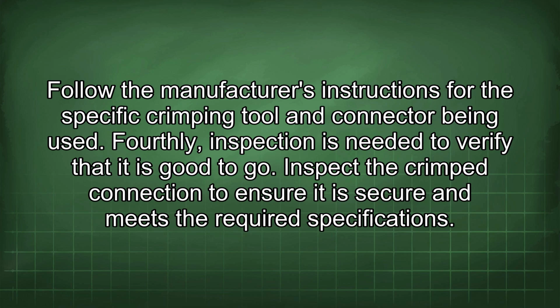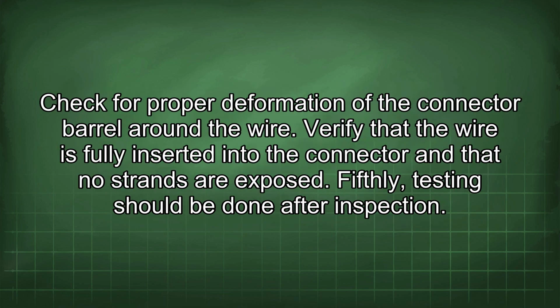Fourthly, inspection is needed to verify that it is good to go. Inspect the crimped connection to ensure it is secure and meets the required specifications. Check for proper deformation of the connector barrel around the wire. Verify that the wire is fully inserted into the connector and that no strands are exposed. Fifthly, testing should be done after inspection.